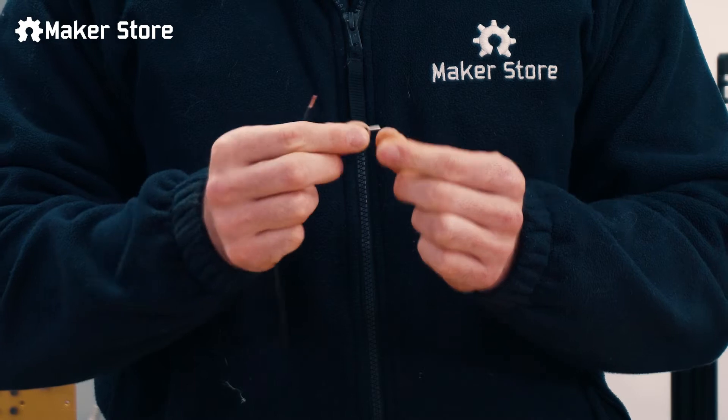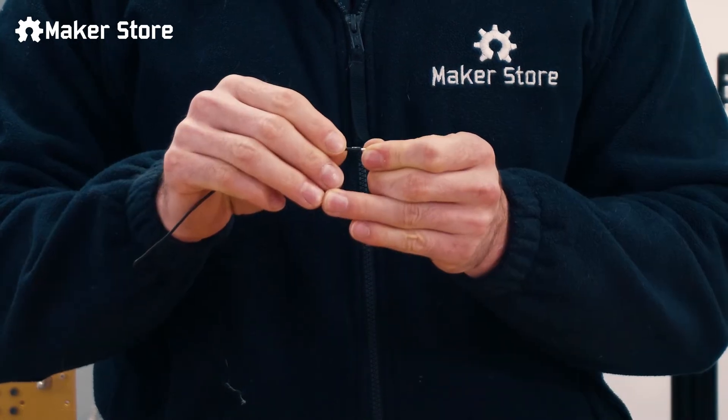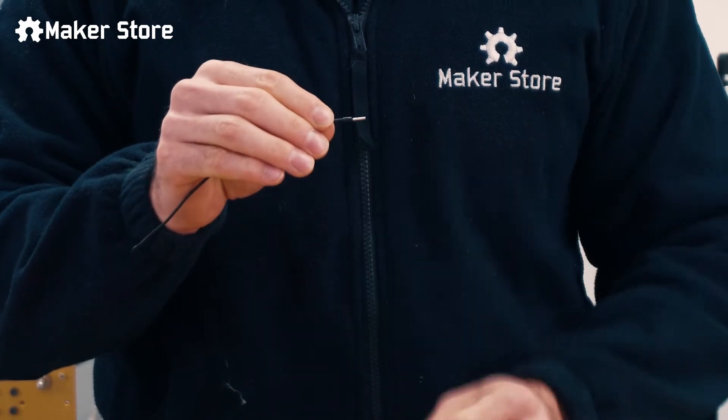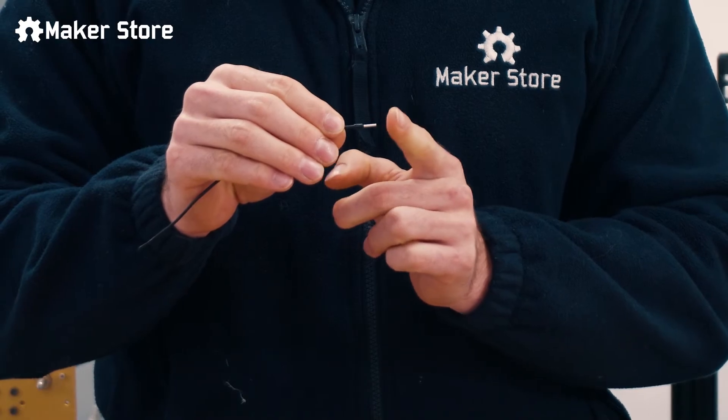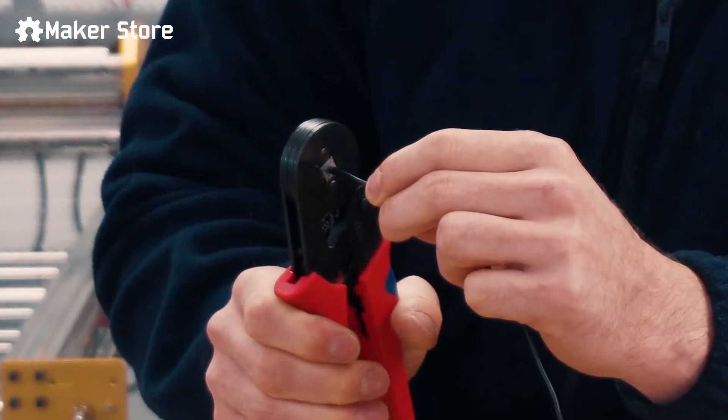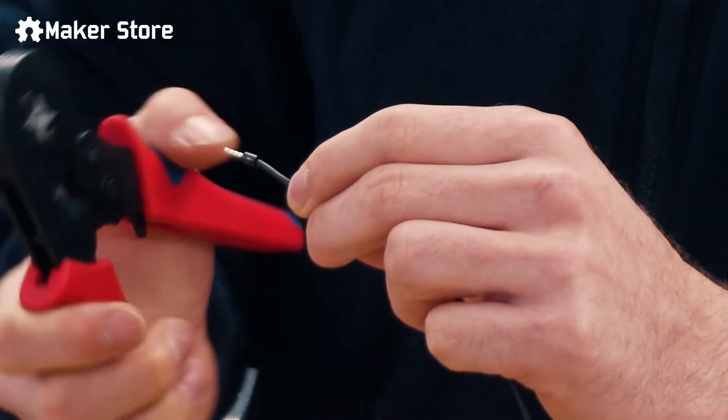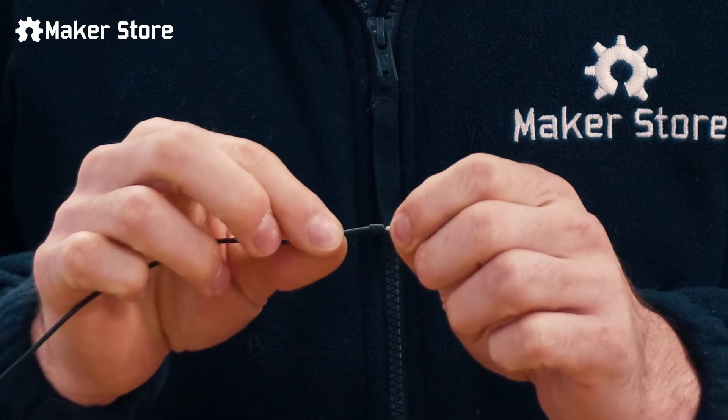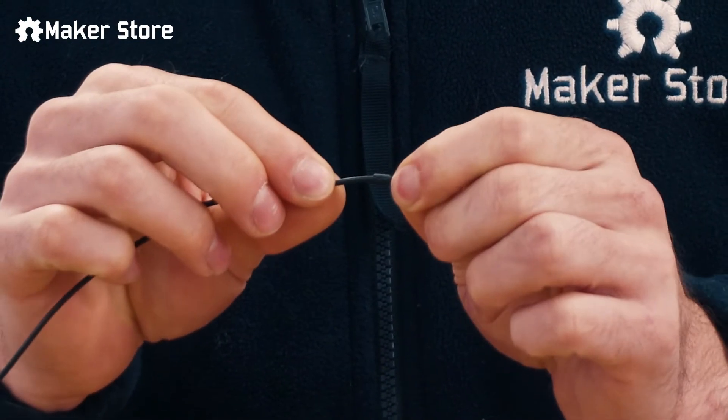Select an appropriate ferrule, apply the ferrule to the end of the wire, covering the exposed end completely. We will now take our crimping tool and crimp the metal part of the ferrule. Tug lightly on the ferrule to make sure you have achieved a strong crimp.